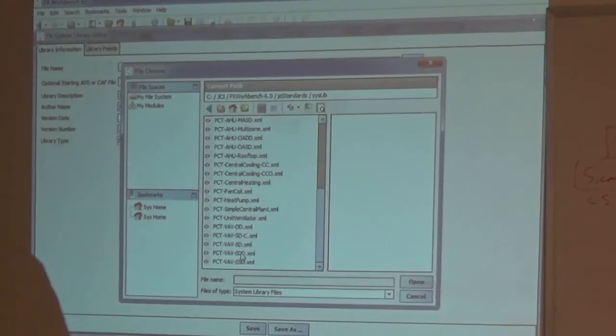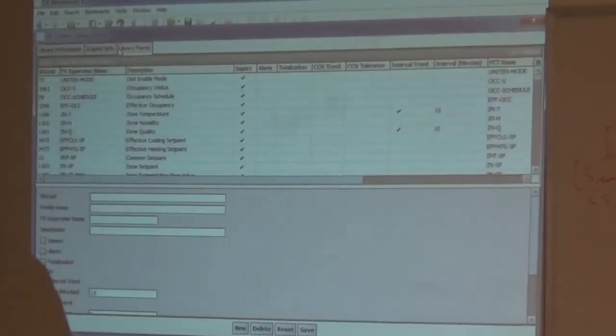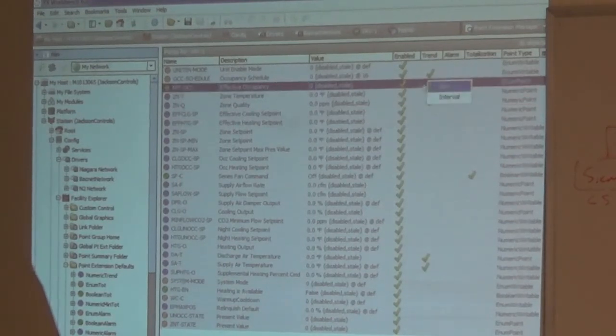Was that a, I think you changed it on a numeric point type and it's an enum. That schedule was an enum. Which one, that you were doing in the list? In this view over here? No, cancel that screen out. That's an enum point you're trying, the effective set point, was that what you were trying to change? Effective occupancy, all right. Oh yeah, see, that one only gives COV now. It only gives that. But down on your point extension defaults, you changed the numeric trend, not the enum. Okay, all right, so that's sort of, oh yeah, well, numeric trend. Yeah, so if I have enumeration trend, still has. There we go, you're right.